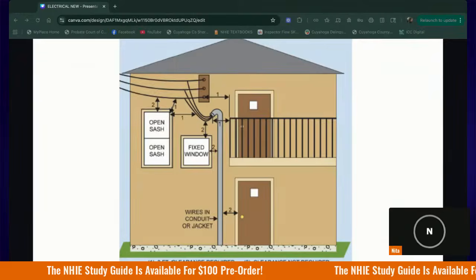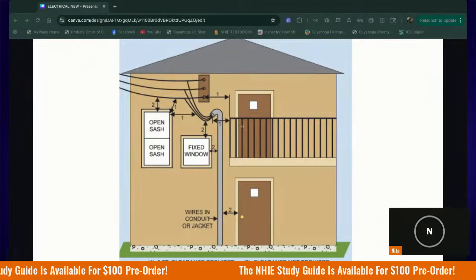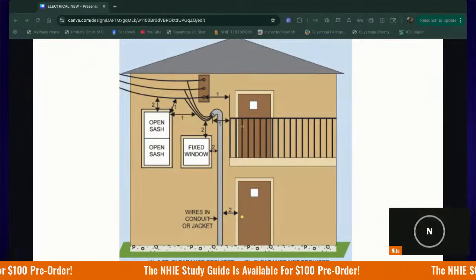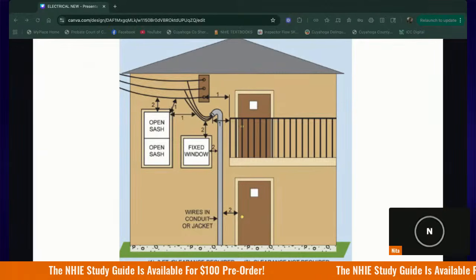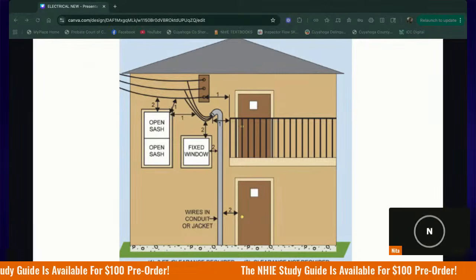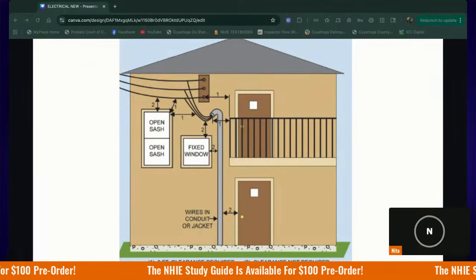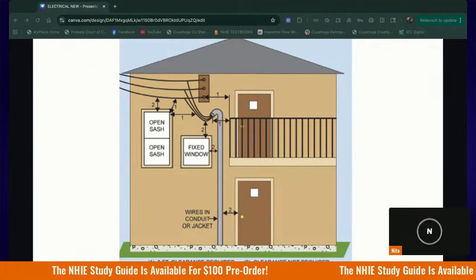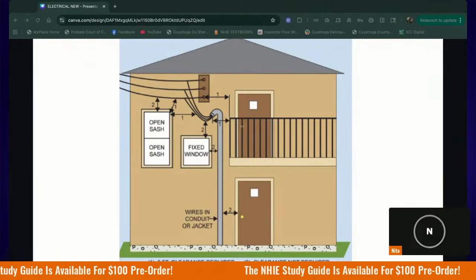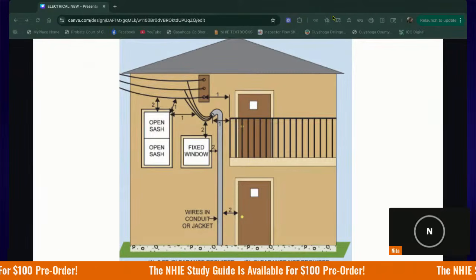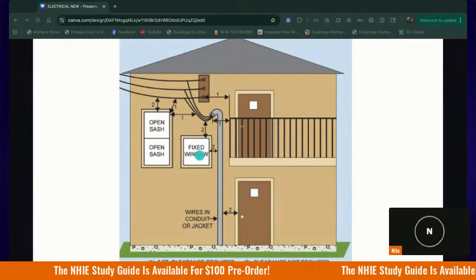Okay. We have the same clearance requirements from windows, doors, and balconies. Basically, think anywhere where there could be people. Any window that can open, if you have an operable window, then your service drop needs to be at least 3 feet horizontally from any window.